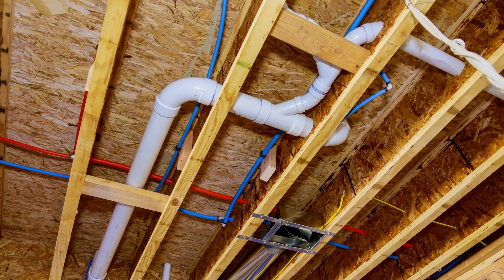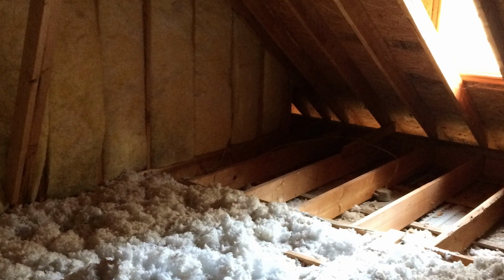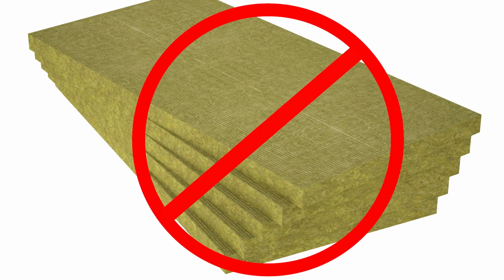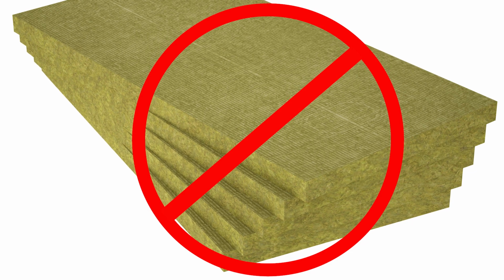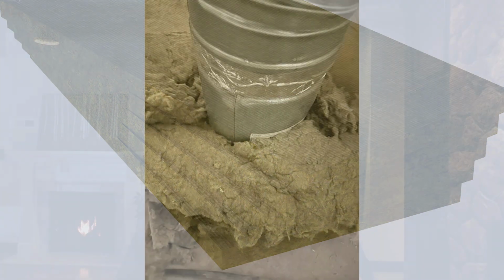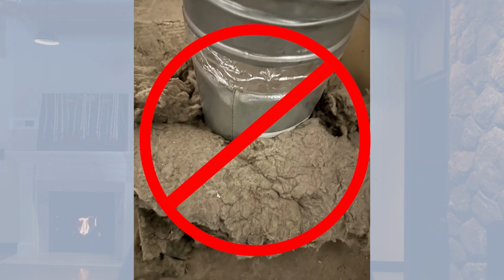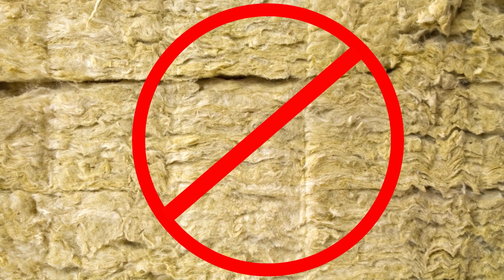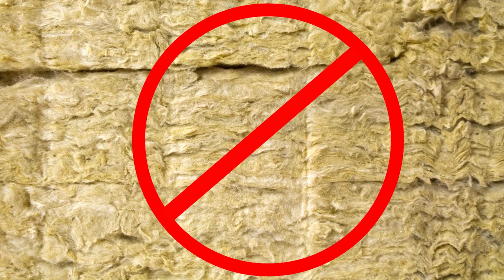Although these are called framing clearances, and it would include all framing, it includes everything else that's going on behind the walls and in the attic area. So that would include blown-in insulation or anything else that might come close to the venting or the fireplace itself. Rock wool or mineral fiber insulation or Thermafiber insulation would also be among some of the things that can't come within the clearances to combustibles to the venting or the fireplace. Although many of these materials may be rated to several thousand degrees, the fireplace and the venting need these airspace requirements to breathe and to cool itself down.